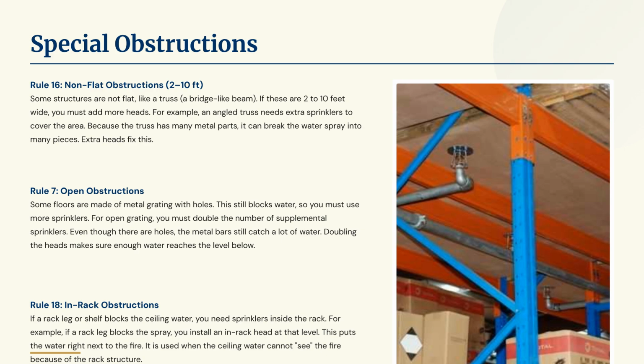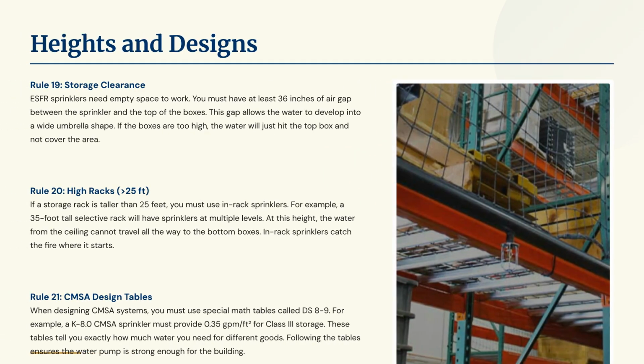Rule 17 mandates doubling supplemental sprinklers for open grating. Rule 18 specifies in-rack sprinklers when rack legs or shelves block the ceiling spray. Rule 19 requires at least 36 inches of clearance between ESFR sprinklers and storage. Rule 20 mandates in-rack sprinklers for storage racks taller than 25 feet.